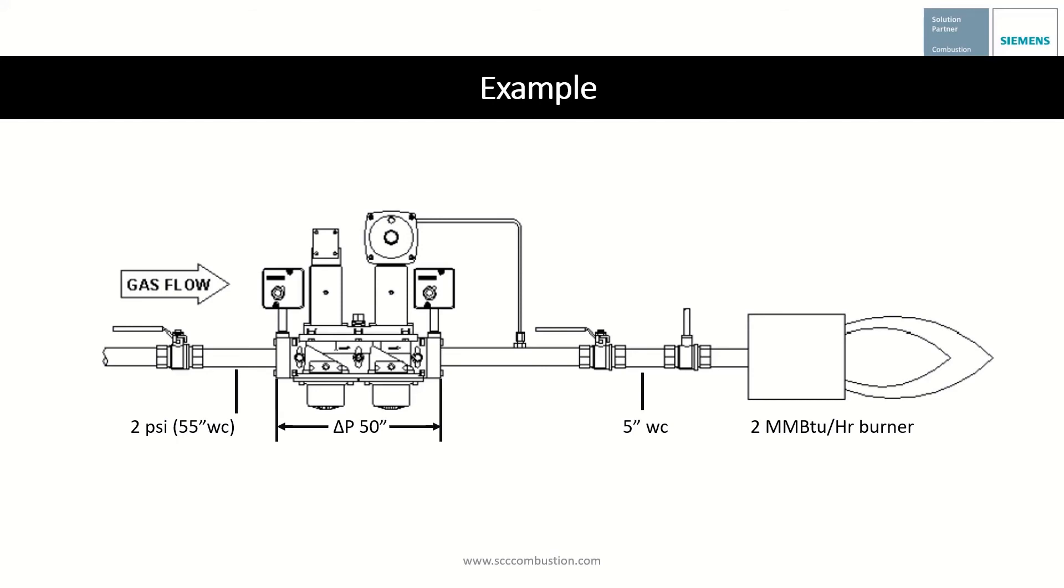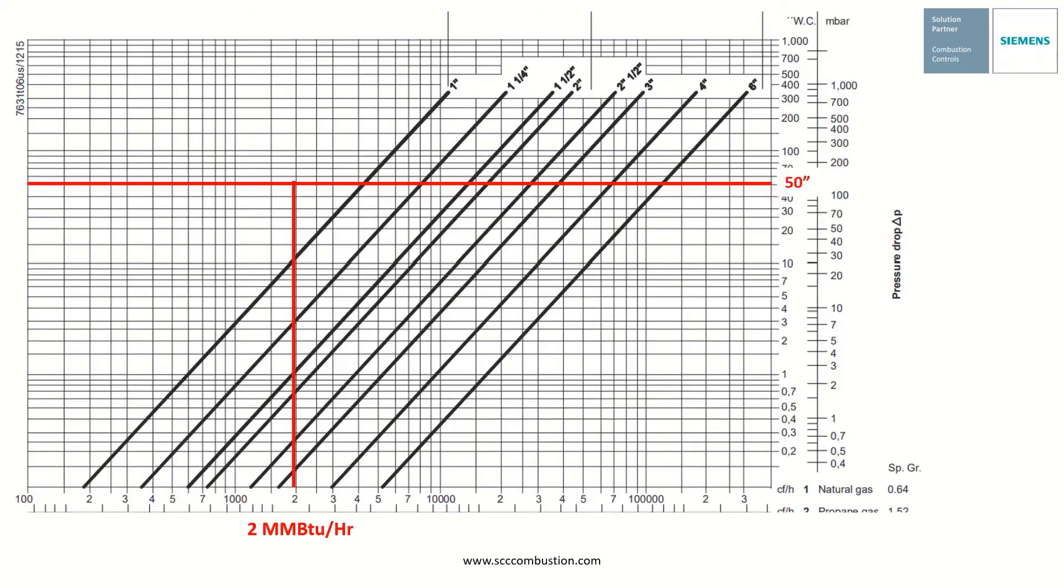Now let's look at the sizing chart to see how small our shutoff valve can go. Here is the sizing chart for Siemens double valves. Our 50 inches available drop and 2 million BTU per hour are marked in red. Our smallest double valve of 1 inch would be the answer here. The 1 inch double valve takes just over 10 inches of drop, which is well below the 50 inches differential available.